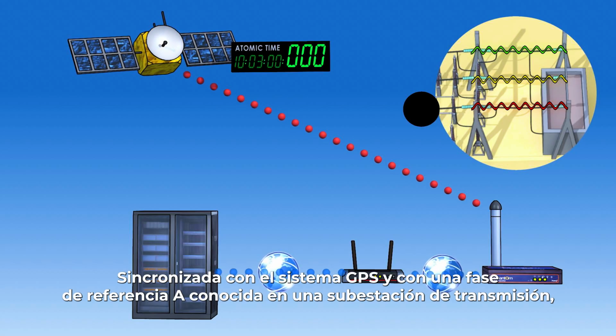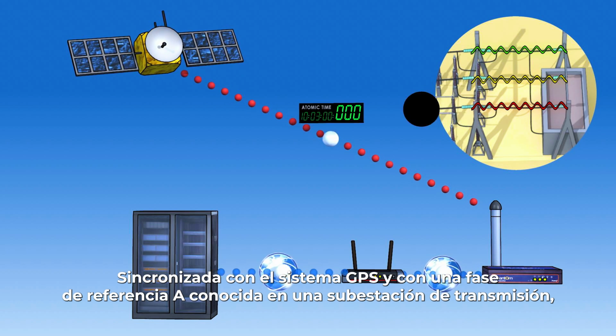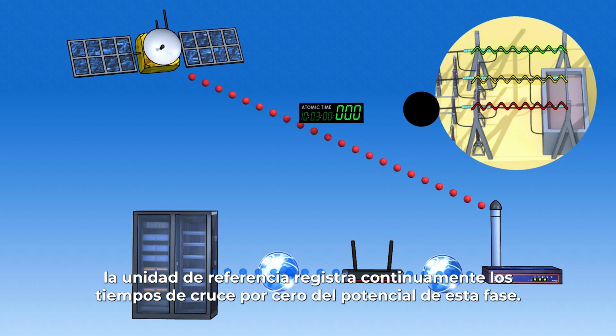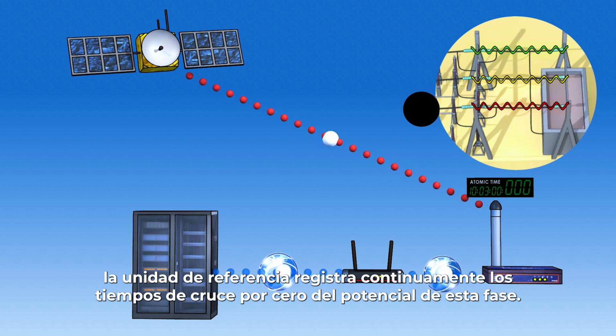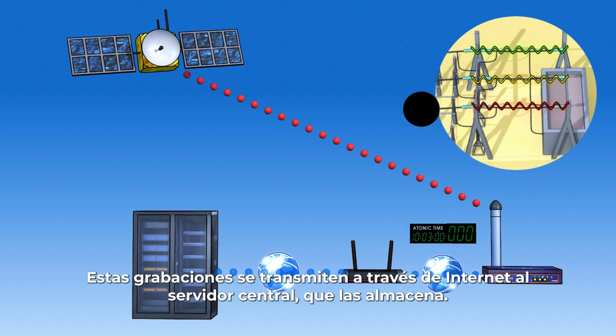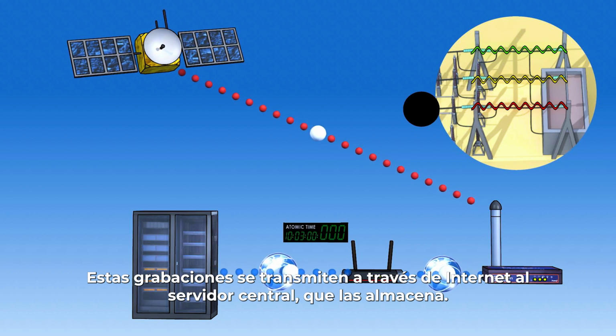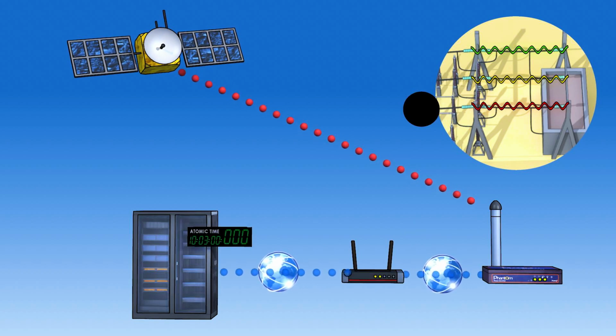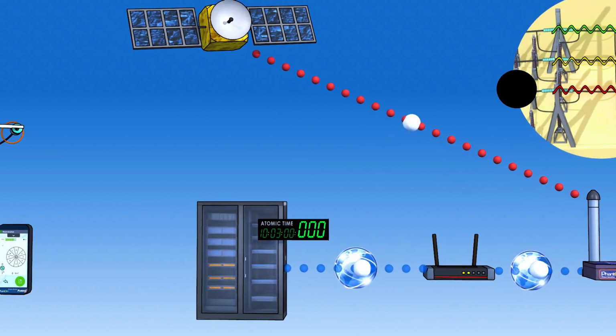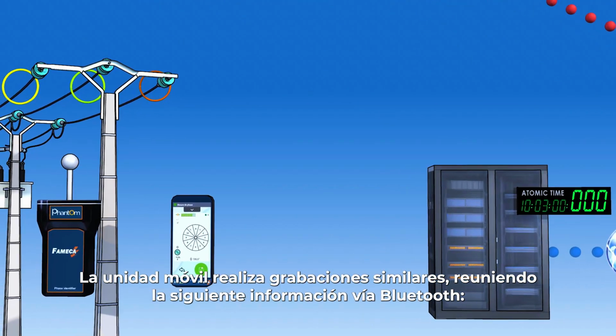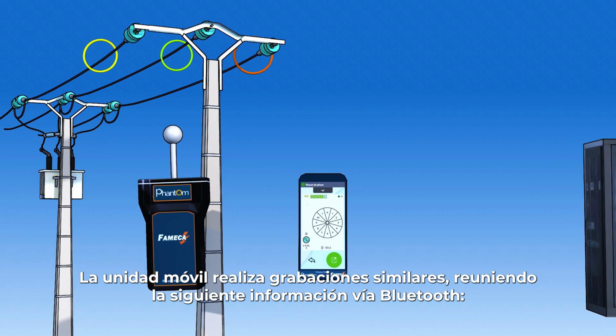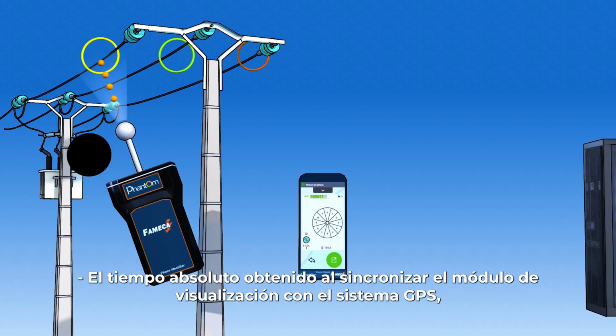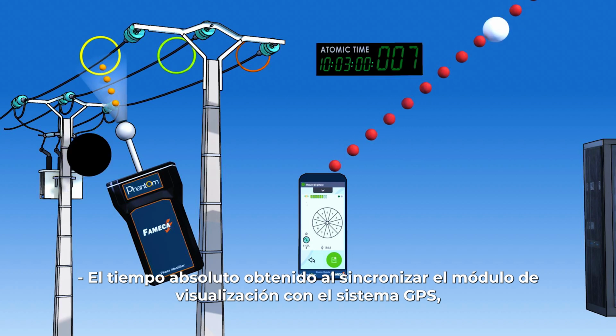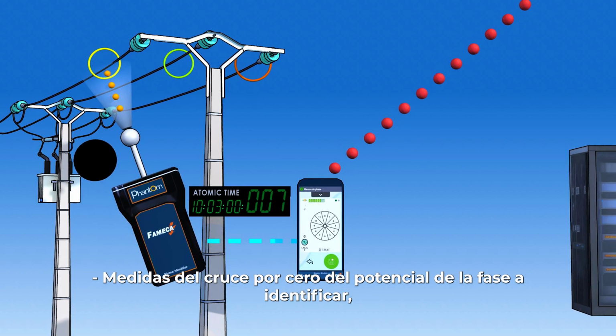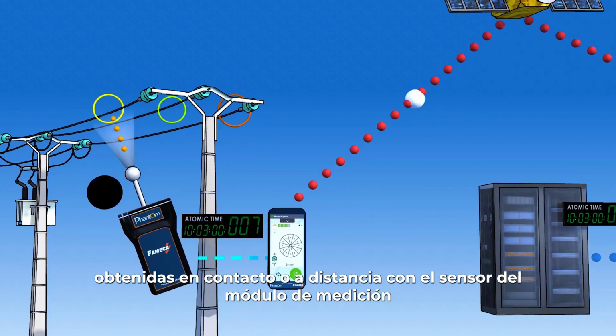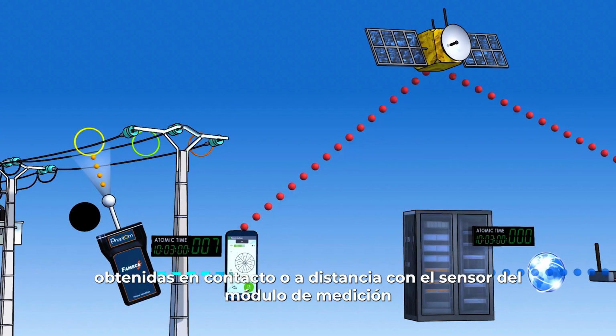Synchronized to the GPS system and to a known reference phase A at a transmission substation, the reference unit continuously records the times of zero crossing of the potential of this phase. These recordings are transmitted via the Internet to the central server, which stores them. The mobile unit makes similar recordings, bringing together the following information via Bluetooth. The absolute time, obtained by synchronizing the display module with the GPS system. Measurements of the zero crossing of the potential of the phase to be identified, obtained in contact or remotely with the sensor of the measurement module.